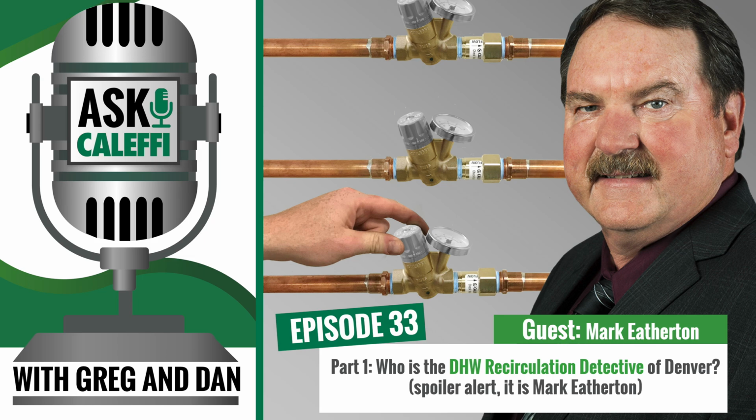But in some of the older systems, you'll have a cross-connected valve, and you find this by recording where people are complaining, and then looking at the map of the property and going, oh, yeah, these are all in the same riser. So you know that problem's coming from down below. But you may get people on the top floor that are spread out horizontally through the whole thing complaining of never being able to get any hot water. And the engineering department or the maintenance people are like, well, let's turn it up. So they turn the water supply temperature up trying to compensate for this, when in reality, there's a failed check valve on the circulation return, which is allowing cold water to run backwards through that circulation return.